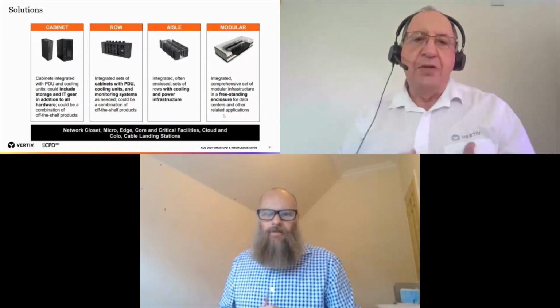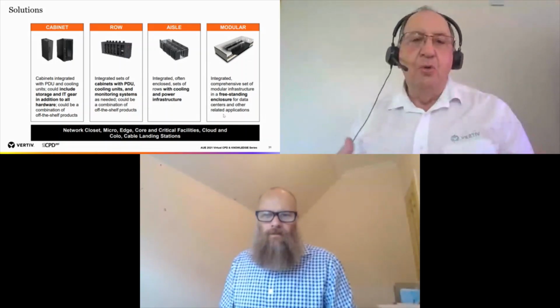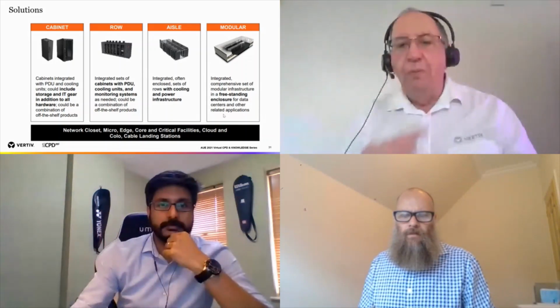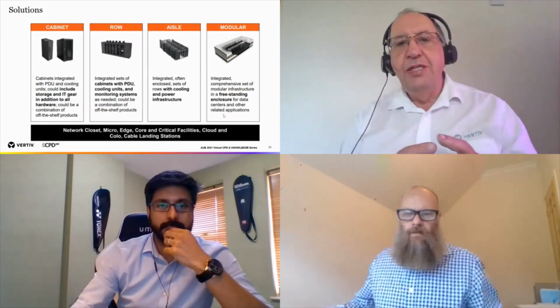And we've got different aspects within the IT space to be able to look after the heat that's being given off by the IT equipment, and in particular, we've got the integrated cabinets that are fully equipped for electrical and mechanical systems. So they've got batteries, UPSs, PDUs, cooling units, all built into one cabinet, bespoke to your application, and they get bigger. The third picture, the aisle picture, shows a system that is sitting in a room.